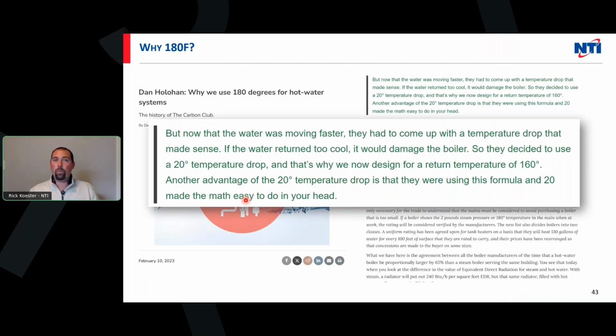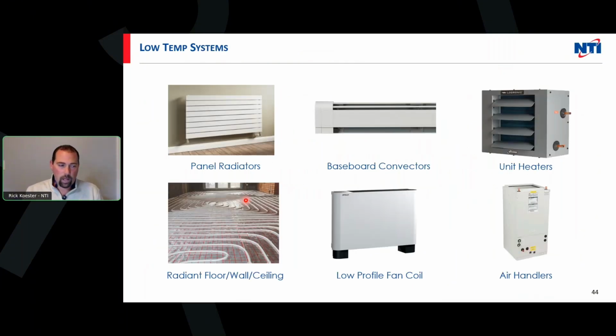And this is where contractors kind of open up for me, because it makes them laugh a little bit. But the reality is we picked 180 degrees in a meeting in 1899, and it's 2025. We created a delta T because the math was easy to do in the head, right? In 1899, and here we are in 2025, and we're still designing systems around a 20-degree delta T, and we're using 180 degrees of water. And that is it. That's the only reason. There's no scientific reason why they use 180 other than that's what they picked, right? So when I talk about this, it gets a lot of funny laughs, and a lot of people are now kind of open to, wow, that's why? Oh, okay. So that's where I hit them with a lot of this manufacturer data.